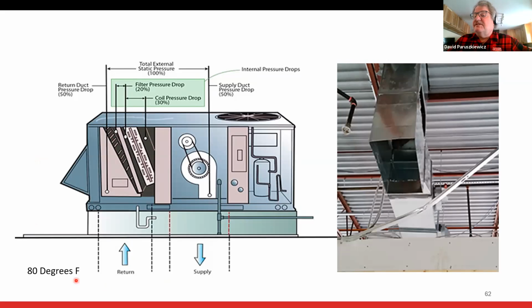And here's just another example. When I'm checking my temperature rise, if I have 80 degrees on the return or higher, even 78, 79, you're going to trip the limit. You're stratifying, you've got to figure out what to do about it. Maybe you extend this return drop. Maybe you move the registers. Whatever you're going to do, you're going to have to do something about it, because if you're in the 80s, it's going to trip.